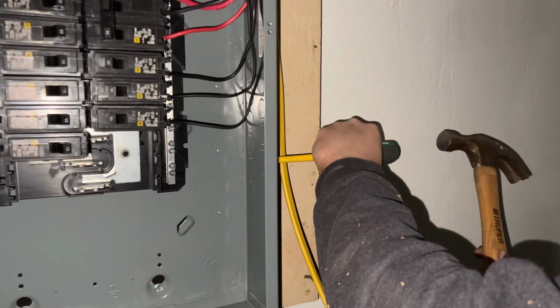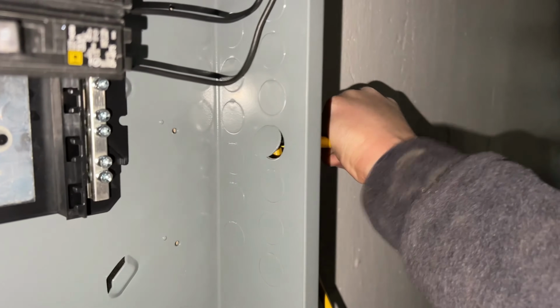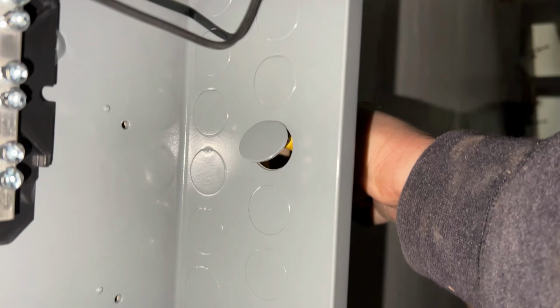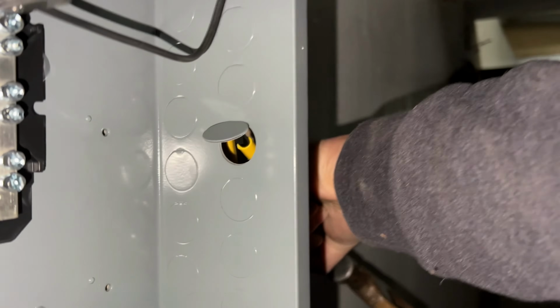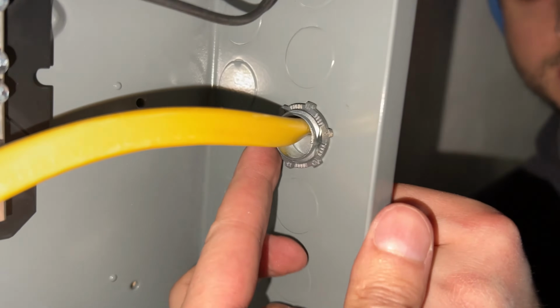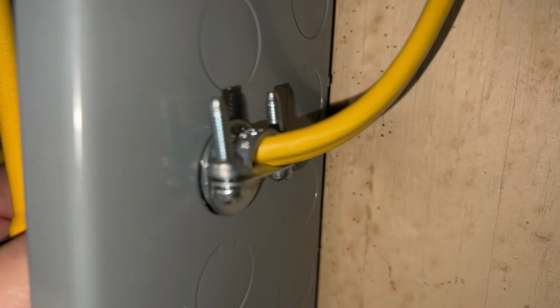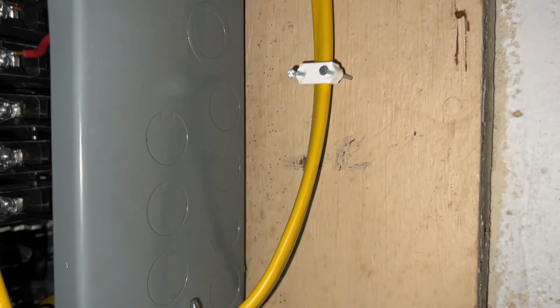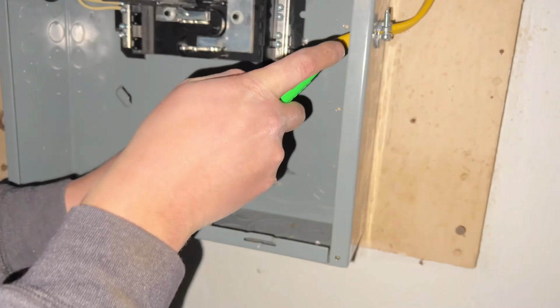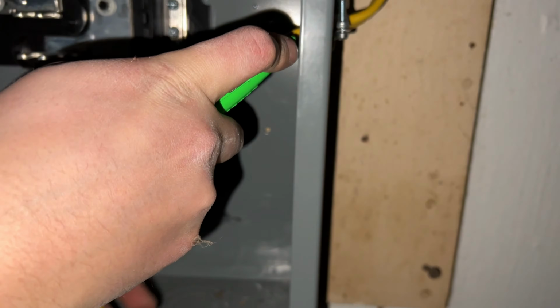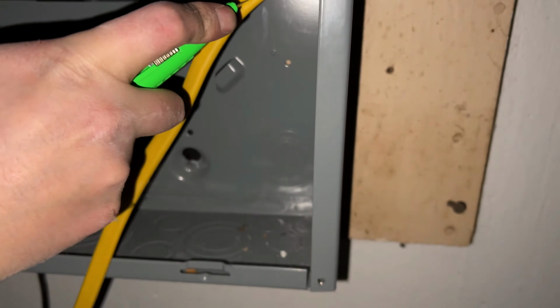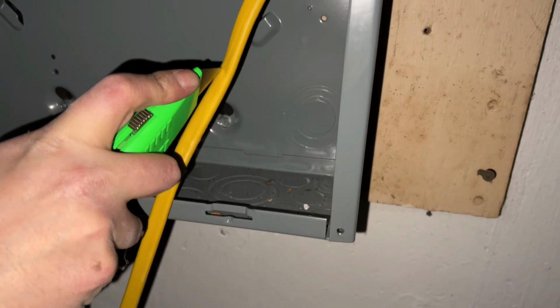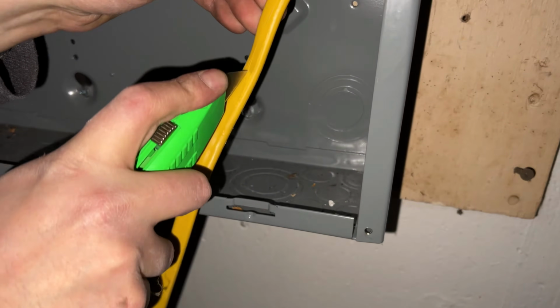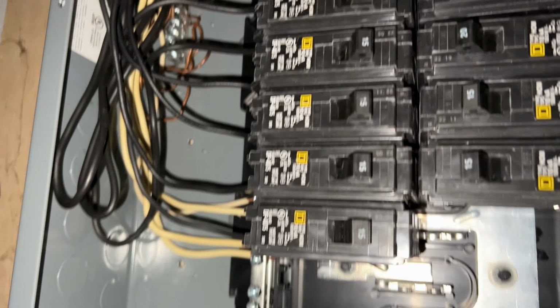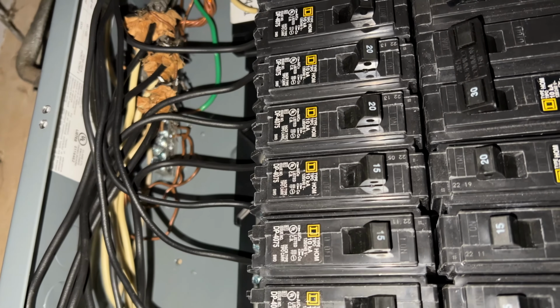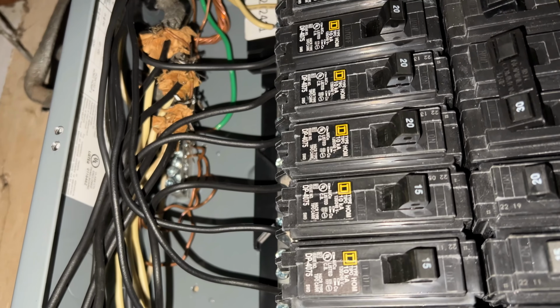With the main power being turned off, you simply knock out the closest location to the main panel, bring your Romex wire in. Do remember to use your strain relief clamp. That clamp is required when going into the main panel box. With the wire securely in place, you're going to simply cut away the insulator, trim it back to within 1/4 inch of the box. You do want to keep the circuit breaker somewhat balanced as far as how many breakers are on the left and the right of the panel.